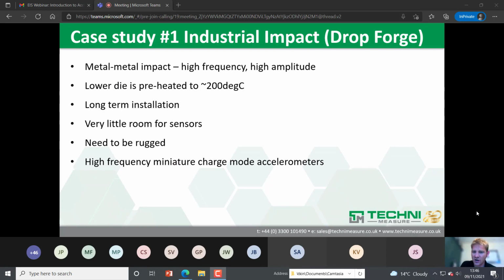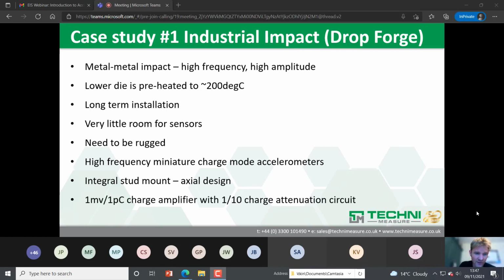So we went with high-frequency miniature charge mode accelerometers. We didn't want the IEPE circuit in the accelerometer because that just wouldn't have survived. The miniature size helps with fitting it in the environment, and the high frequency response with a high resonant frequency allowed us to get the high measurements. Because they're looking at impact measurements, these had an integral stud and an axial design, and these ones did actually have connectors. We used a charge amplifier with a fixed gain of 1 millivolt to 1 picocoulomb, and because it was such a high amplitude measurement, a charge attenuation circuit ahead of the charge amplifier to attenuate the charge even further, so we could measure the full response.